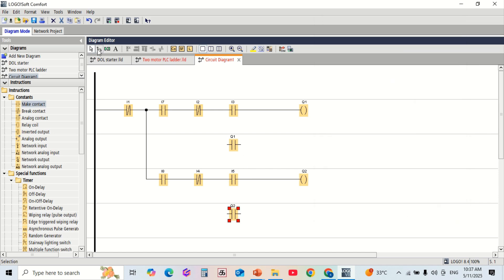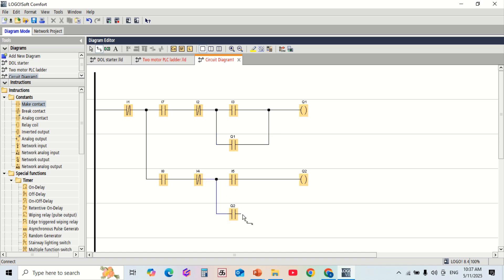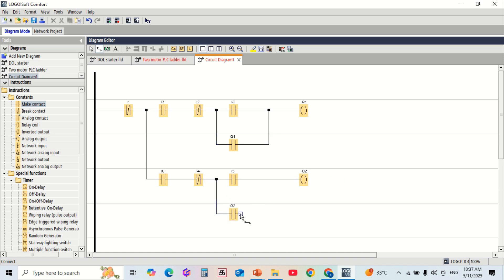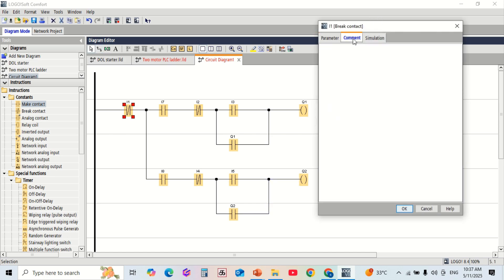To keep the motor running after releasing the start push button, add a self-holding contact in parallel with the start input. Use Q1 as a self-holding contact for motor 1 and Q2 for motor 2 — this is the latching or self-holding purpose.